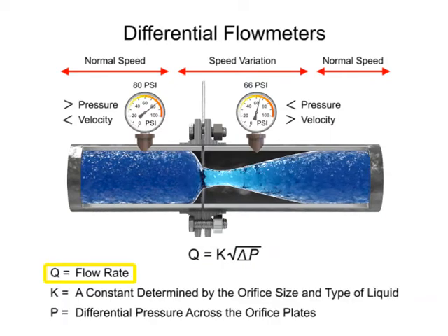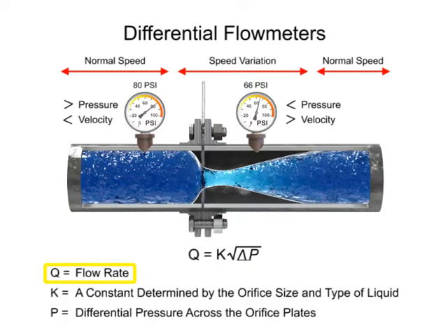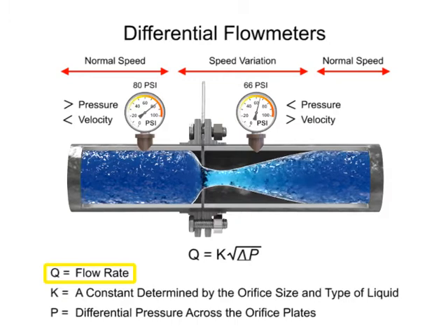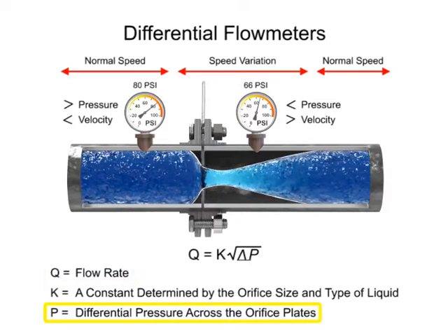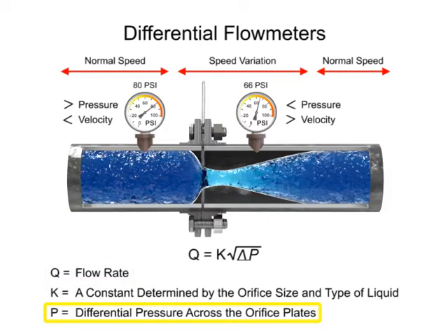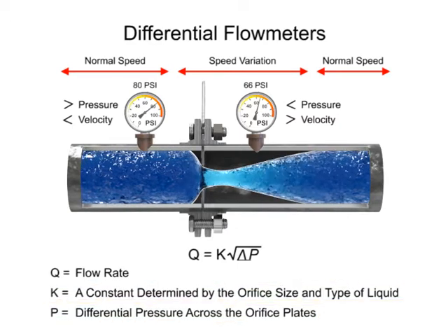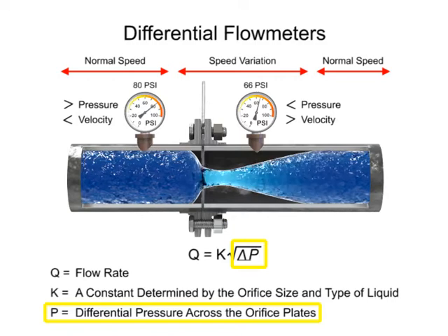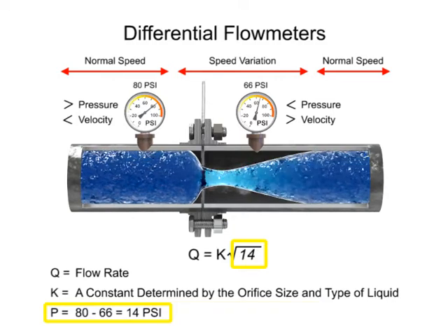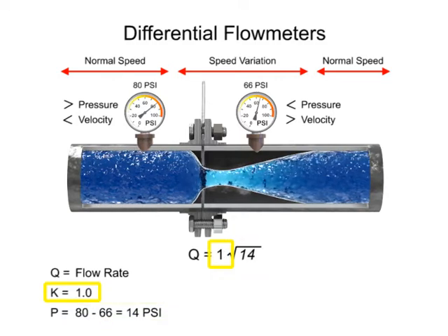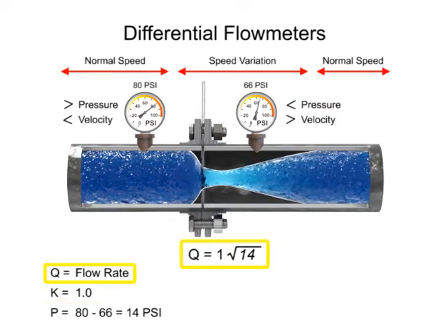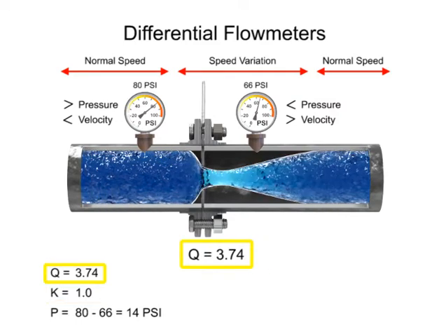The flow rate, Q, of a fluid through an orifice plate increases in proportion to the square root of the pressure difference on each side multiplied by the k-factor. For example, if the differential pressure increases by 14 psi with a k-factor of 1, the flow rate is increased by 3.74.